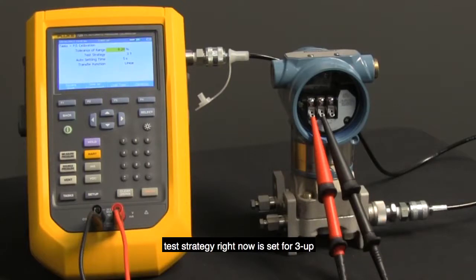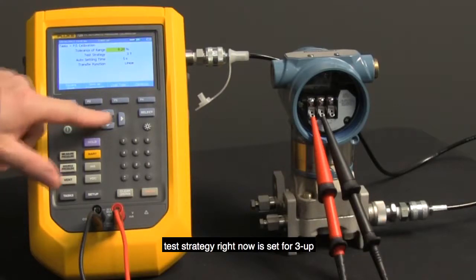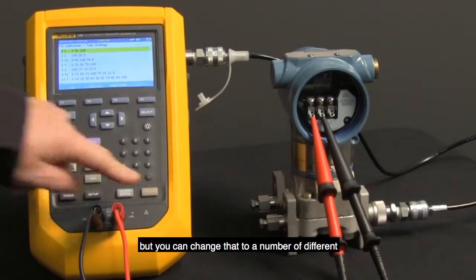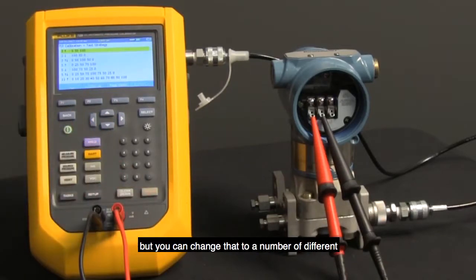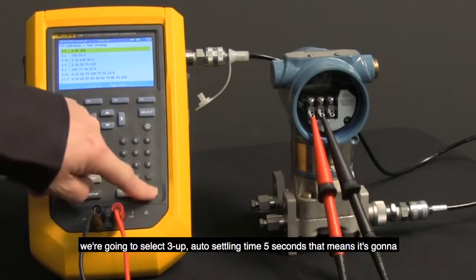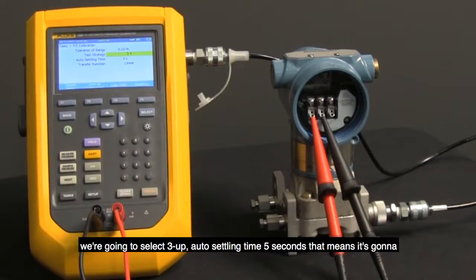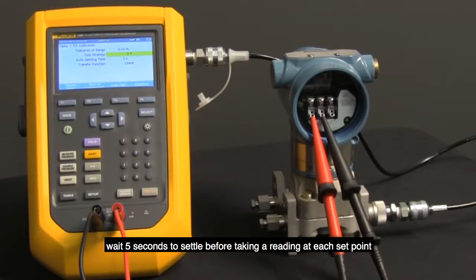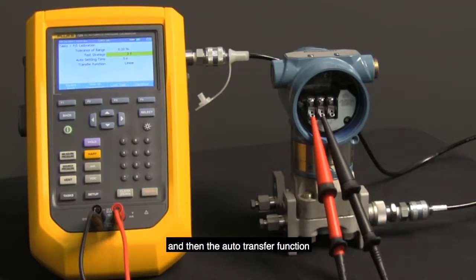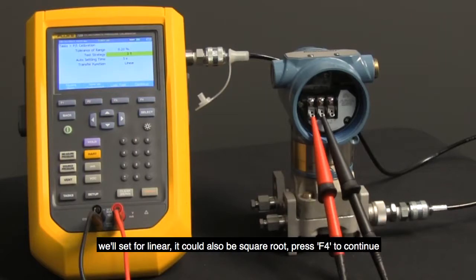Test strategy right now is set for 3 up, but you could change that to a number of different preset calibration strategy test points. Again, we're going to select 3 up. Auto settling time, 5 seconds. That means it's going to wait 5 seconds to settle before taking a reading at each set point. And then the auto transfer function is set for linear. It could also be square root. Press F4 to continue.